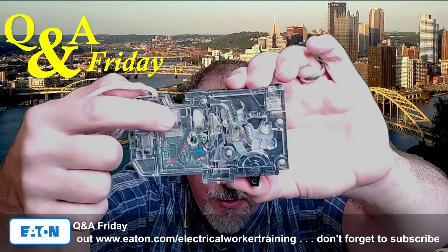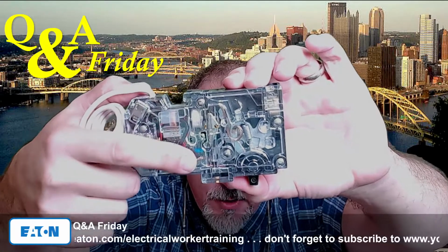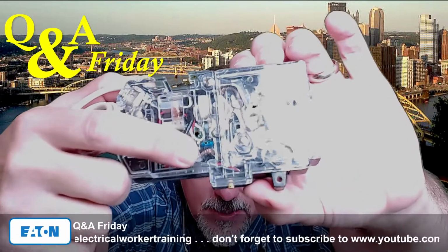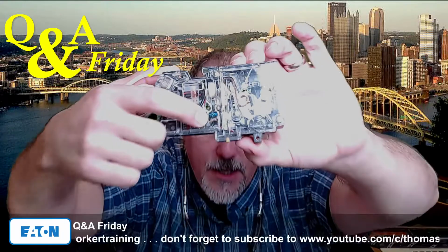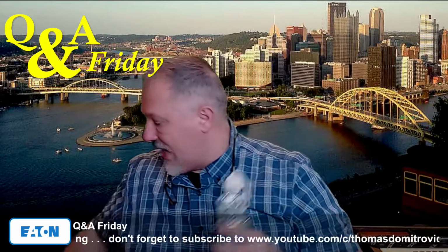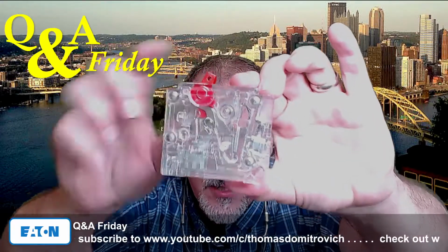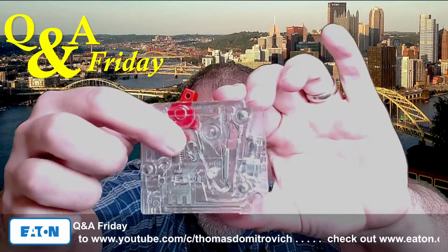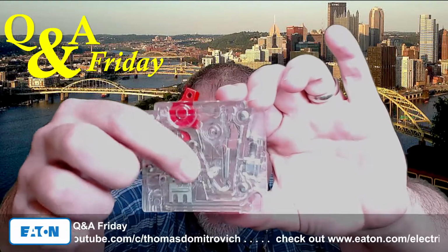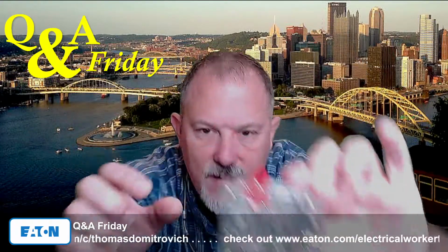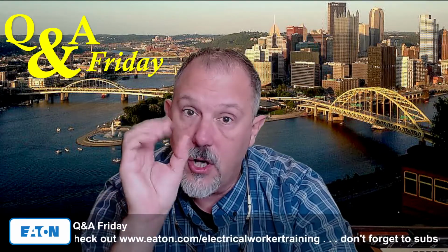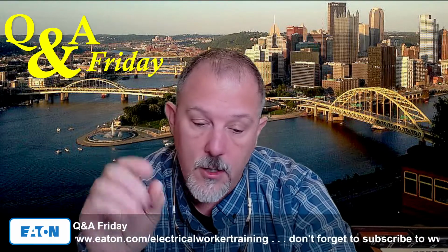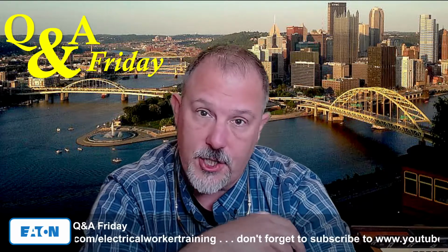And you'll see this black wire that's going through here, and you'll see a bare copper conductor right there. And this one's standard thermomagnetic breaker. You'll see that stranded wire right here. And what is that? That's a flexible conductor inside of this circuit breaker that connects the contacts, which are moving, with the termination, right?